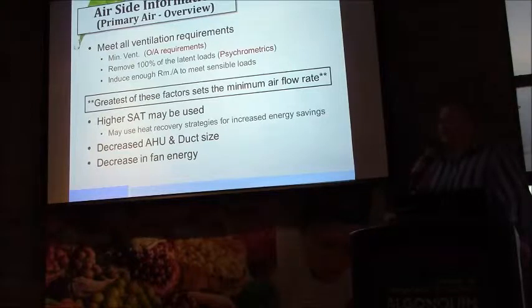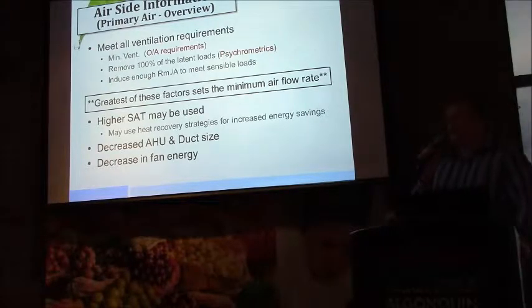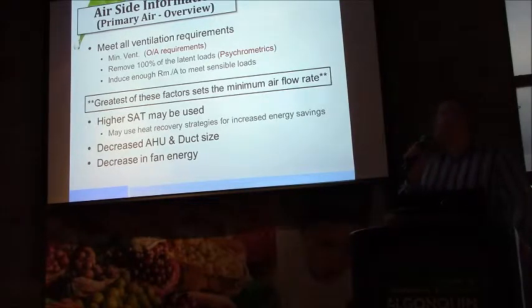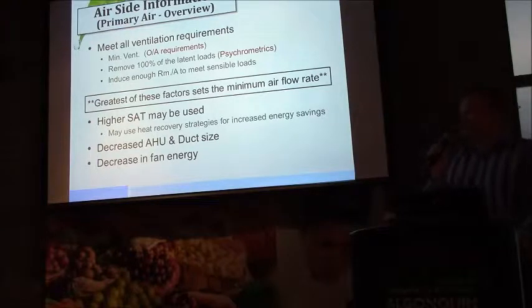And the simplest way and the most accurate way to determine whether or not a beam is appropriate for a space is to run the psychrometrics on the loads. So we look at the actual data that's mined from the load calculations to determine whether or not a beam is appropriate for that space. And all beams are not appropriate for every space. There are instances where we'll find that the latent load drives our primary air to too high a volume that detracts from its use, or that we're so close to being able to manage the sensible load, given the design conditions that we chose on the primary air dew point or the room design condition, as to negate its effectiveness. And fundamentally, we let the psychrometrics or the loads guide us to determine whether or not a beam is right for the space.